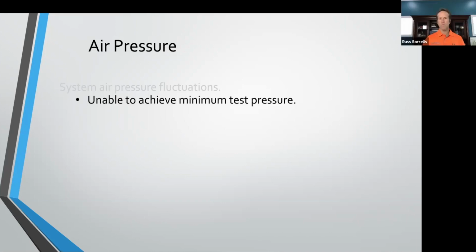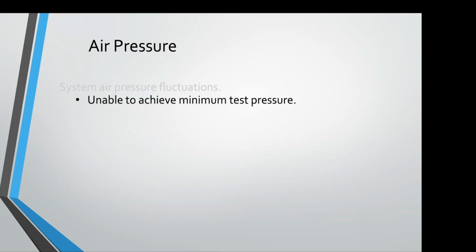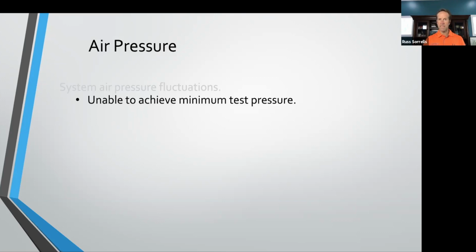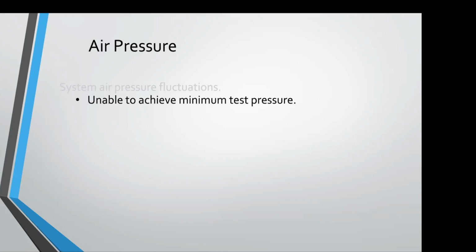What can happen is customers, I see this often, they'll set that window too tight. And so what happens is let's say it's 50 PSI and their air pressure settings for whatever reason are actually about 49.5. And they go to run a test and they have pressure loss during the test, but before it actually stabilizes, in that stabilized time, it drops below the 49 PSI. So if they've set the window 49 to 51, it drops below 49, it's going to immediately reject as a severe leak because the pressure went below the minimum test pressure. Again, it's a way to prevent running through that entire cycle, right?